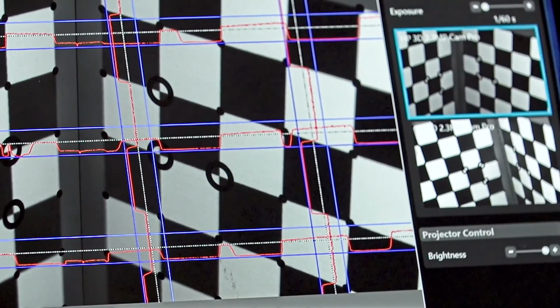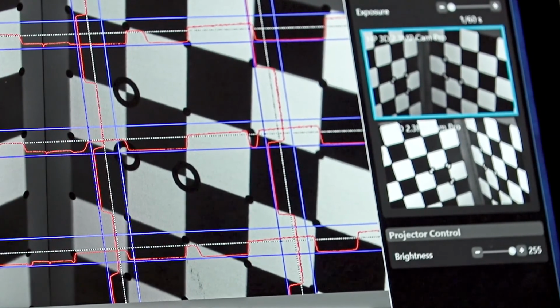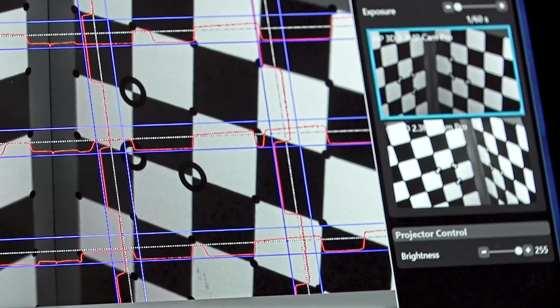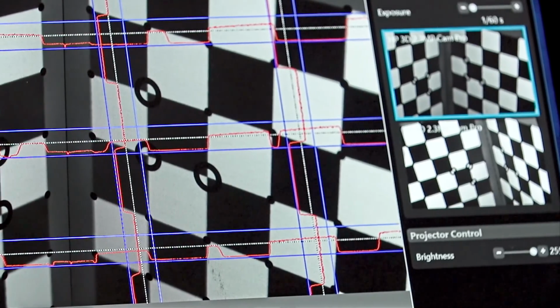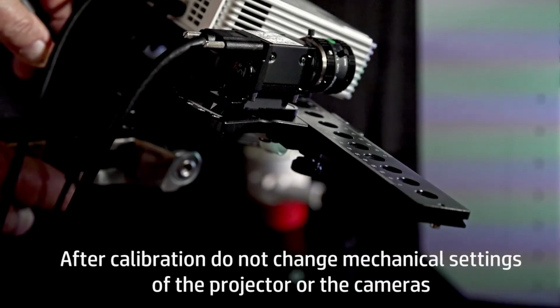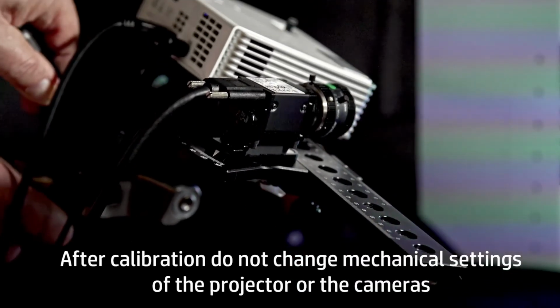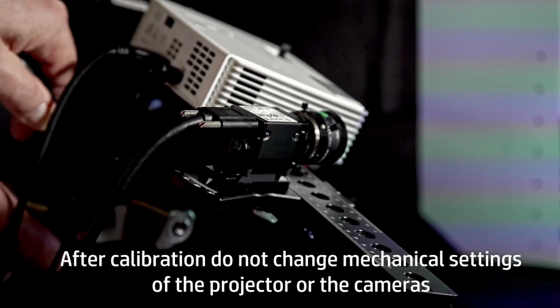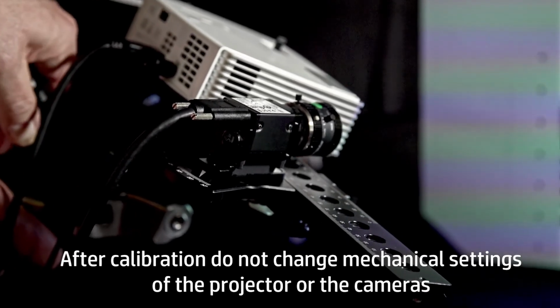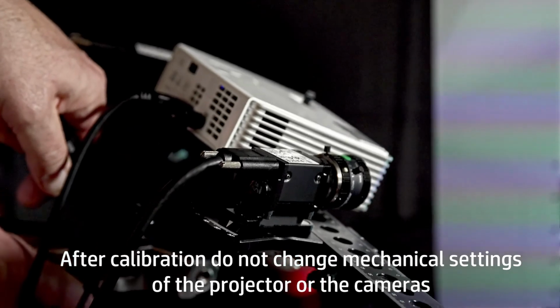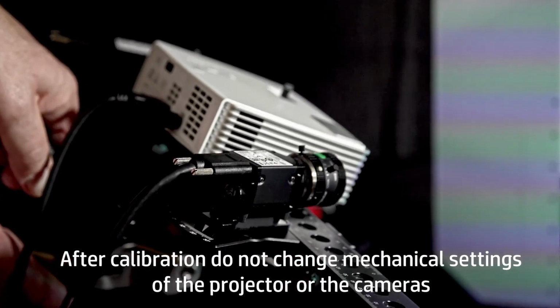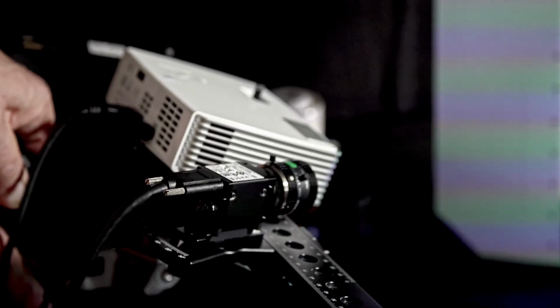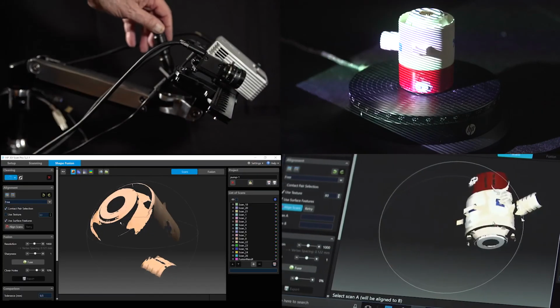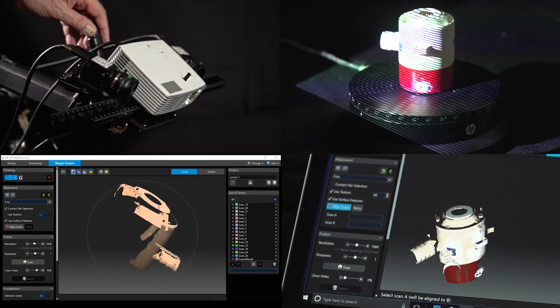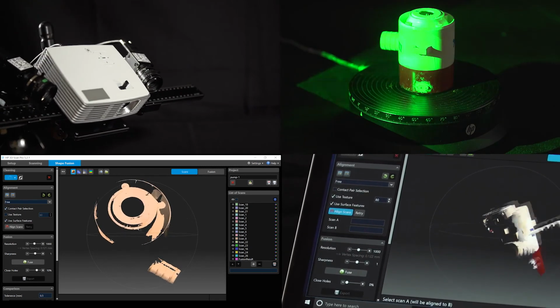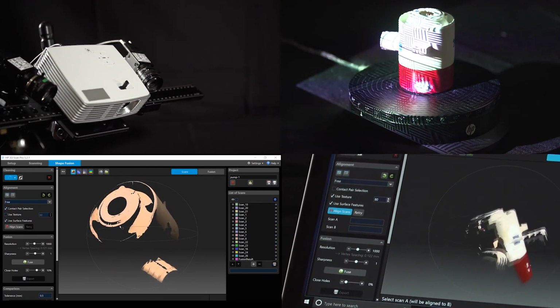You can now move, rotate, or tilt the scanner assembly without losing the calibration setting. Powering down the equipment and closing the software program will not change the calibration. This ends part 1 of the tutorial, Setup and Calibration. In part 2, scanning will be demonstrated.